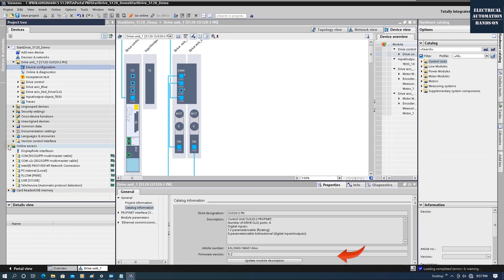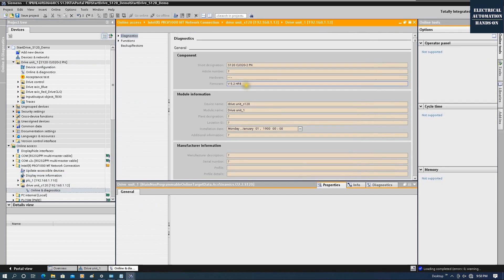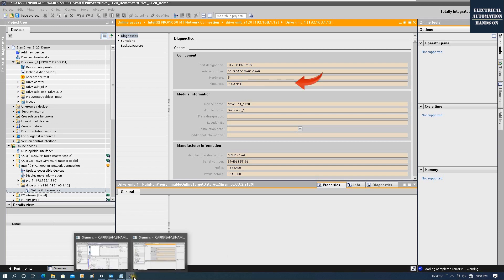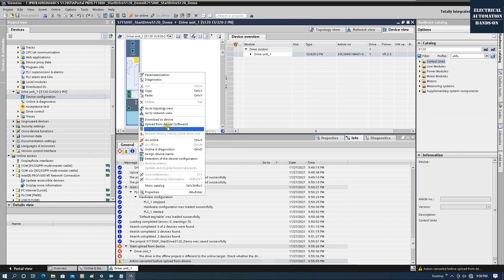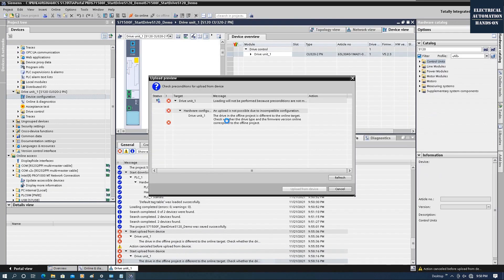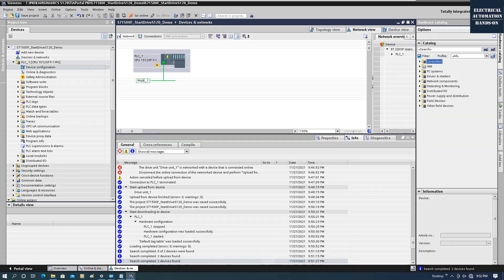From offline, we can check the firmware version here. Or we can go online — double-click under Diagnostics — and here we can see the current firmware version from the CU: that's version 5.2. If you accidentally select the wrong firmware version when you do the upload, you will see this error code: 'An upload is not possible due to incompatible configuration.' So we know our current firmware version is 5.2.